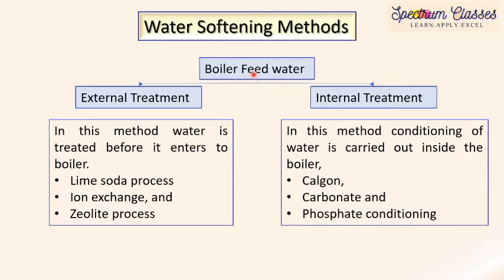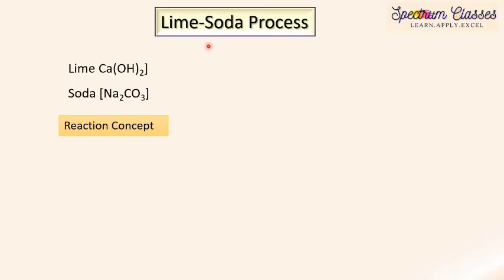For boiler feed water treatment, there are two methods: external treatment and internal treatment. In external treatment, water is treated before it is fed to the boiler. In internal treatment, conditioning is done inside the boiler. External methods include the lime soda process and ion exchange process; internal treatment includes carbonate conditioning and phosphate conditioning.